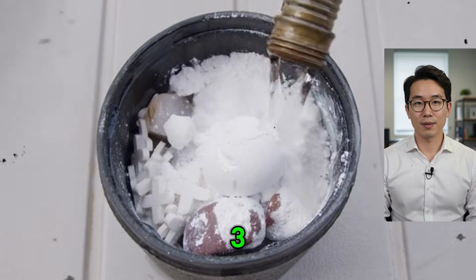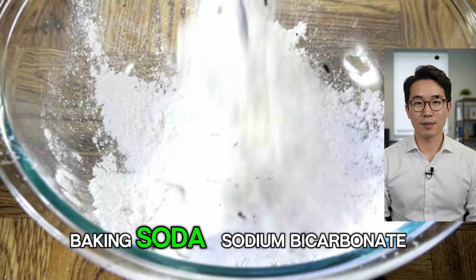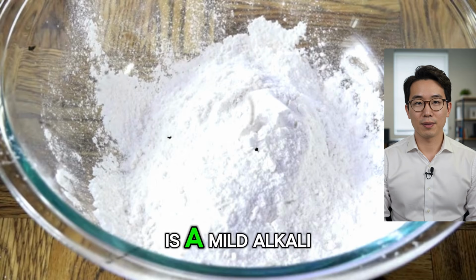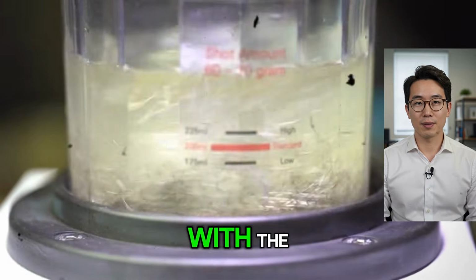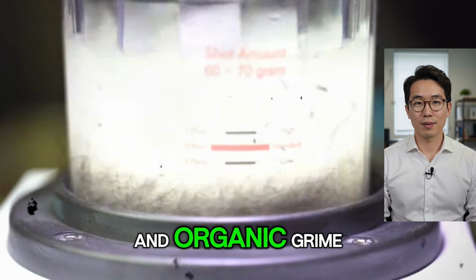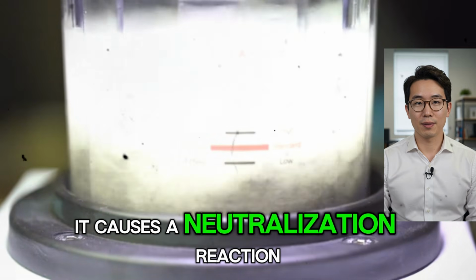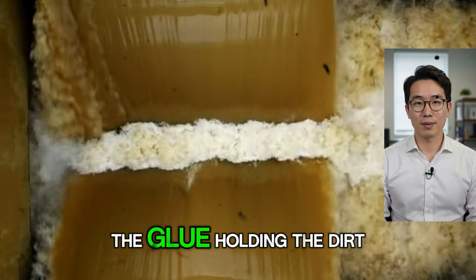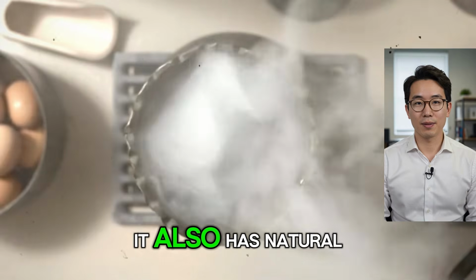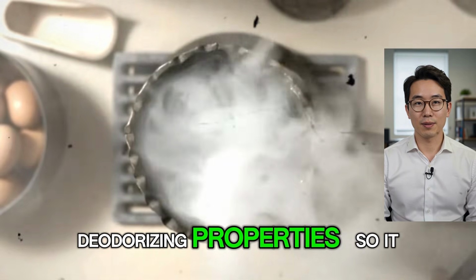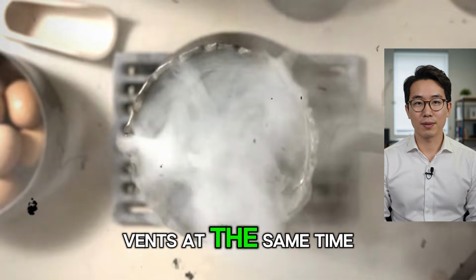Now here's where our $3 chemistry comes in. Baking soda, sodium bicarbonate, is a mild alkali. When it comes into contact with the acids in mold, biofilm, and organic grime, it causes a neutralization reaction. It literally dissolves the glue holding the dirt to the fins. It also has natural deodorizing properties, so it kills the musty smell coming from your vents at the same time.